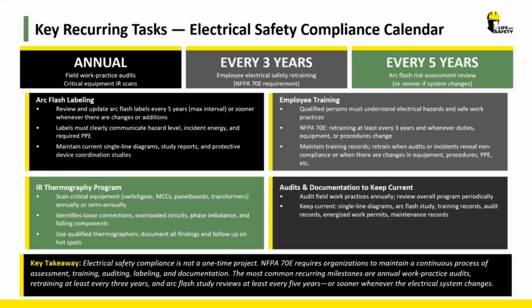If you're looking at the presentation, these are more geared toward maintenance activities, what's required on NFPA 70B and NFPA 70E for maintenance activities on industrial control panels. But as a practice, these also apply to your energy storage systems. Whether they're sitting in inventory or on warehouse shelves, they should be scanned periodically for thermal readings.